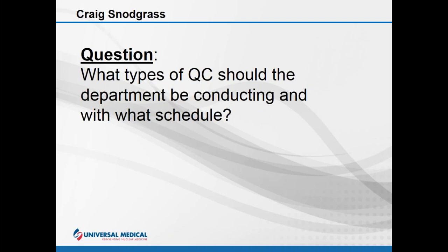Another check would be intrinsic QC. Most of our customers perform this more on a weekly basis. By completing both of these checks regularly and tracking your QC numbers, customers will have a better understanding and feel for their system and how it's operating, and will know ahead of time if there's some QC image quality that's not at its best.